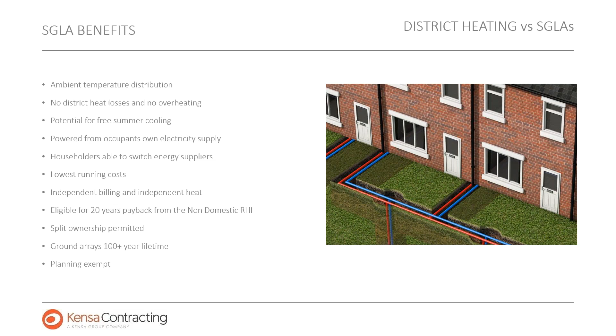So Ajay very kindly mentioned the Shoebox Unit, which is being utilised on those projects for Energiesprong. This is it. This has been specifically designed for multiple unit installations. It was designed actually to fit in a 600 by 600 kitchen cupboard. And on that very first slide I showed you with the heat pump and how it works, this is the outside of the unit. So all of those components, the pump, the heat exchangers, the compressor are all installed inside that individual shoebox system.